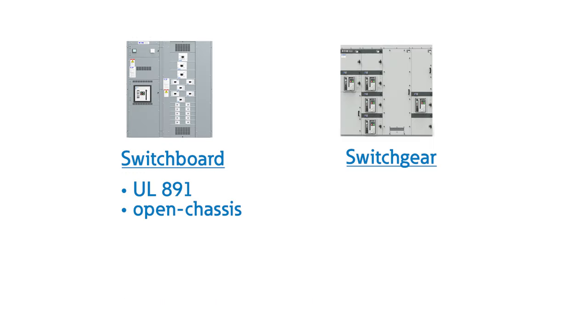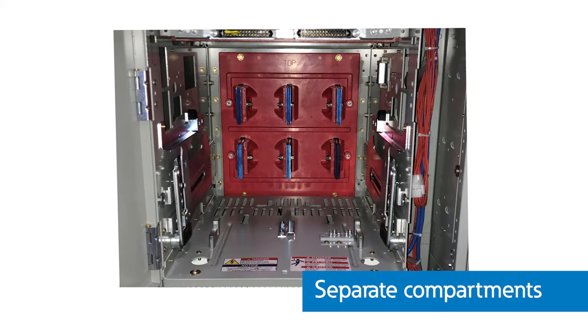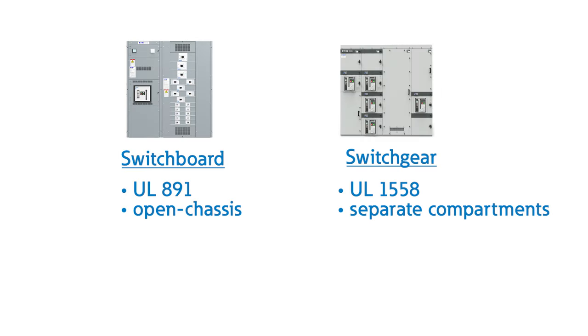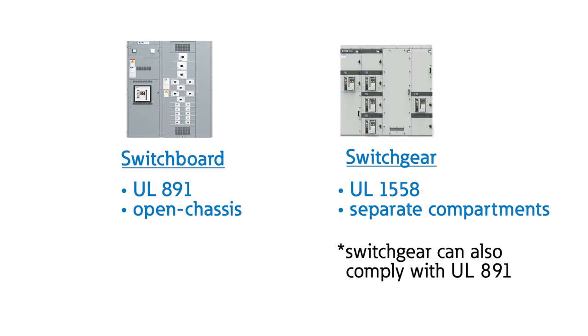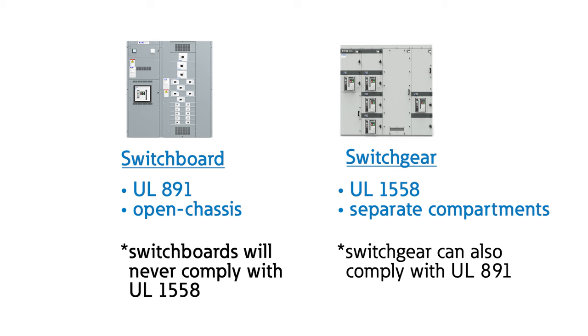This differs from switchgear, which, under UL1558, requires separate compartments to shield and isolate each section from another. Because of this structural difference, switchgear can be designed to fulfill UL891 switchboard requirements, but switchboards can never satisfy UL1558 switchgear standards.